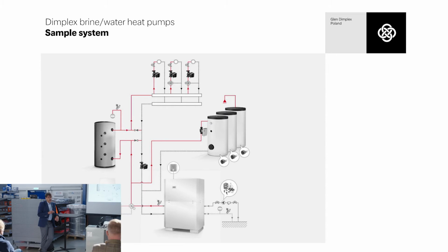Also pretty much the same diagram for operating in regular condition, but the difference is, of course, that here we have a different heat source. In this case, it is the drilling, the boreholes in the ground. But the hydronics inside the building and inside the plant, the setup of the system, is pretty much the same, and the functionality and the controlling also are the same. In the standard situation, we control the return temperature from the installation, and it is the main measurement point for controlling all processes with this diagram.